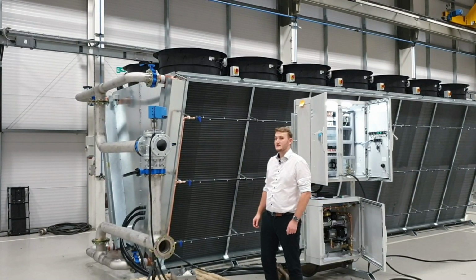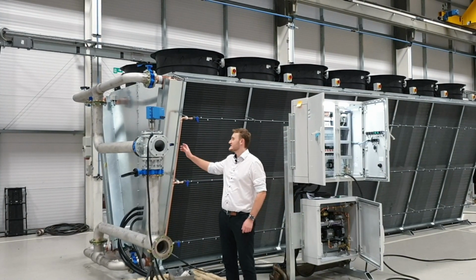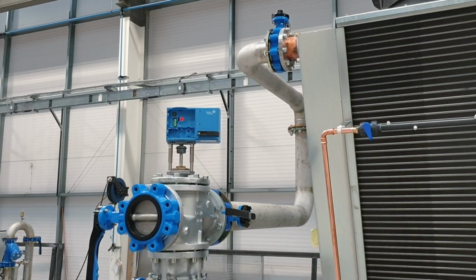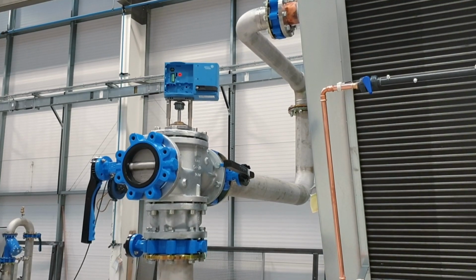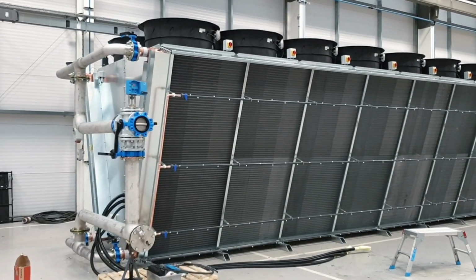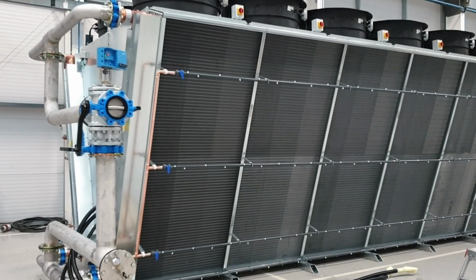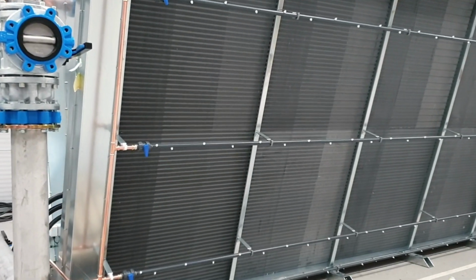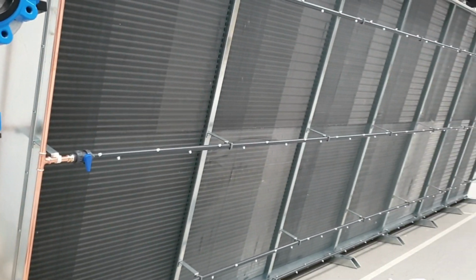This cooler uses our overcooling prevention system. As you can see here, this is a 3-way diverting valve. So it means that over the coldest portions of the year, where we might be getting too much cooling, we can bypass as much flow as needed in order to regulate the temperature in the data hall.